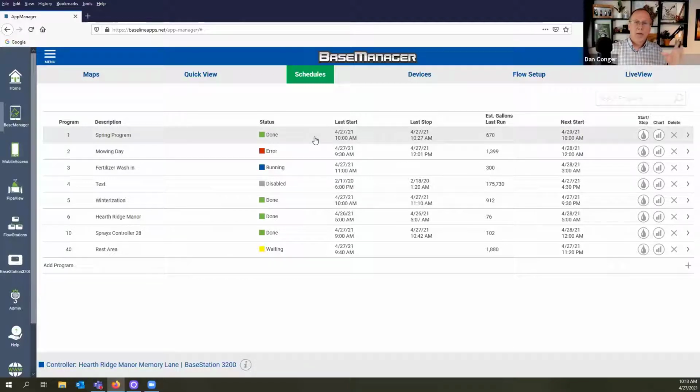And then you're going to change the concurrency on that just based off of the size of the heads. So, yeah. It's a very common question, when someone's out in the field and they've called me in the past: how do I get the controller to run multiple zones at one time? They may not have a flow meter, and if they do, they haven't done a learn flow. So it's not about flow. They know which zones they want to run together, or they know it doesn't matter. Any 2 zones can always run on this system. Sometimes it's just very simplistic like that, but they want to know how to go in and set that up.